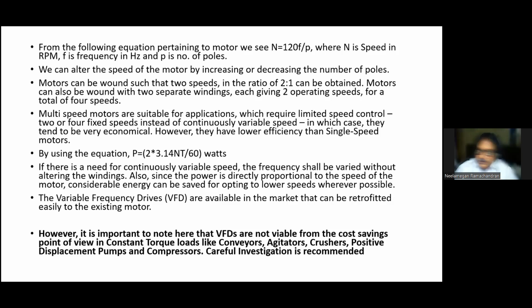So in the equation, when the speed is decreased, the torque is going to increase. So for constant torque or constant power requirements, VFD is not recommended. Only for variable torque loads like blowers and AHUs can we use VFD to good effect. Constant torque loads are like conveyors, agitators, crushers, positive displacement pumps and compressors. With VFD compressors, I am talking about screw compressors where the torque is constant. VFD is not going to be of much use.